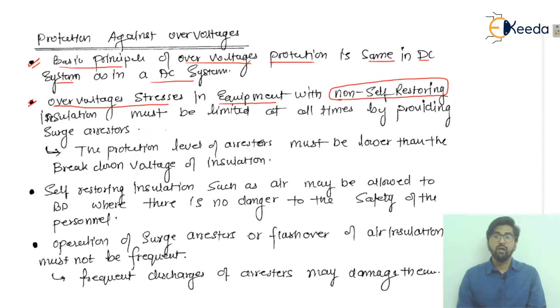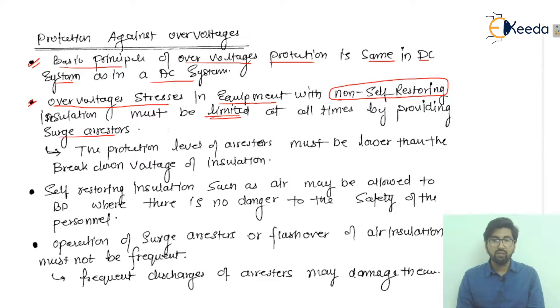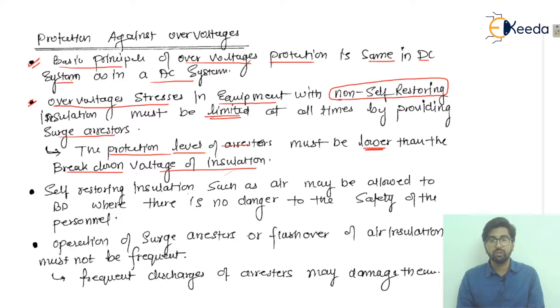These stresses must be limited at all times by providing surge arrestors. The protection level of the arrestors must be lower than the breakdown voltage of the insulation.